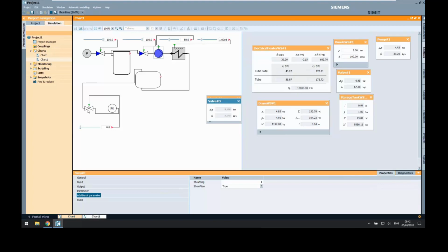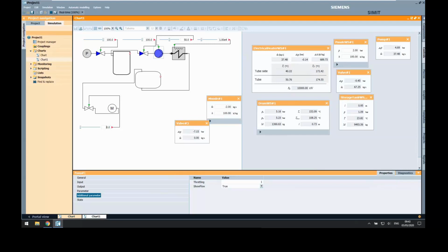And if I wanted, I could now simply start using my steam. Sorry. There you go. 2 grams per second of consumption, and we should see, this now is increasing slower. If I close the valve, I will see that we are now losing the steam from the cylinder.